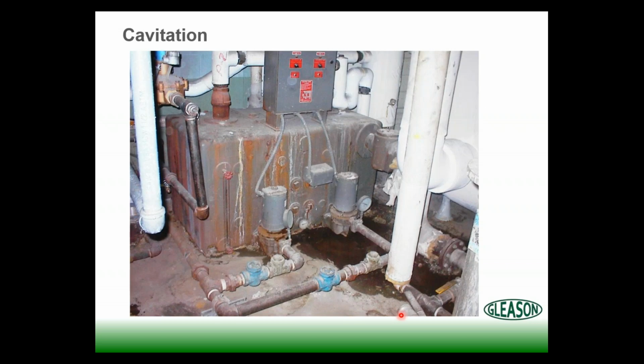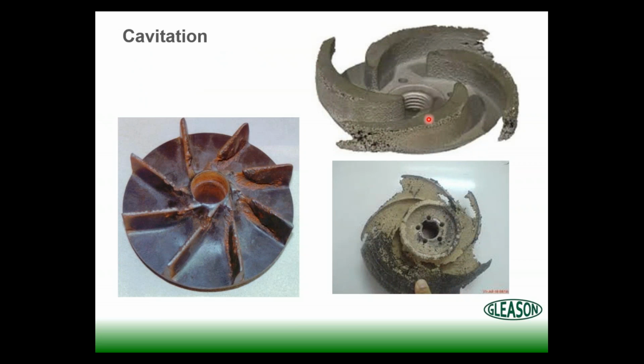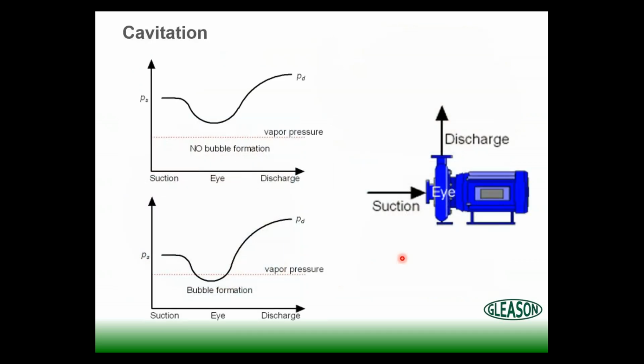So, condensate pumps, cavitation, real quick, I'll make this real quick. It can do a lot of damage to impellers. And when we're talking about cavitation, what's happening here, remember, these are condensate pumps. That condensate is extremely hot. And when very, very hot condensate comes into the eye of this impeller and it sees a lower pressure area in the eye, a percentage of that very hot condensate is going to flash.